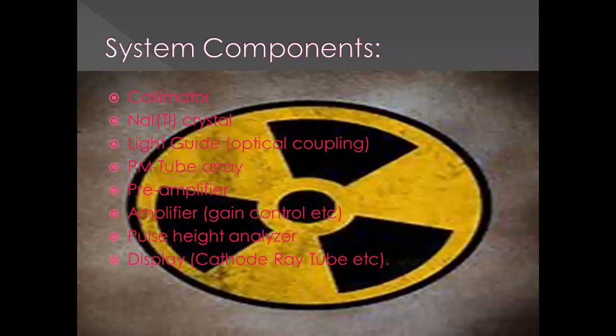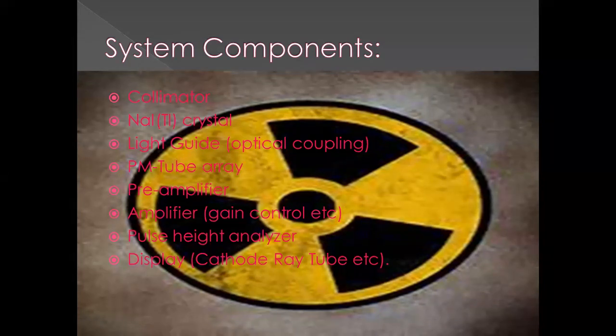Basically, inside the gamma camera we have a collimator, a filter made of lead, and a sodium iodide crystal. We also have light guides and optical coupling, a PMT tube, a preamplifier, a pulse height analyzer, and lastly a display cathode ray tube. These are the materials inside the gamma camera.